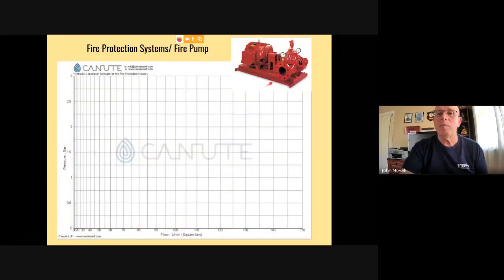All right, so fire pumps. Again, depending on where you come from, you may have a lot of experience with fire pumps. You may have no experience with fire pumps. So just to give you an idea of why fire pumps are in buildings, it's all based on hydraulics. So the fire pump we put in a building is basically almost the same fire pump that you have on your fire apparatus. Right? Centrifugal fire pump, more likely than not.